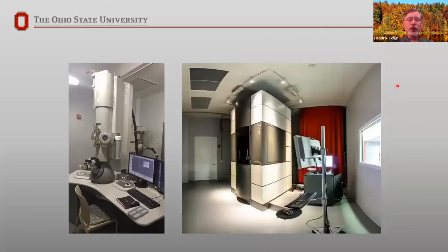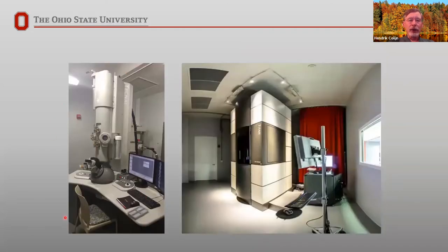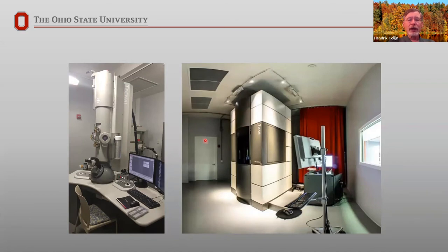The microscopes themselves look something like this. This is our Tecnai 30, with a 300 kV electron source at the top — electrons accelerated to 300 kilovolts — coming down through the condenser lenses, the sample on the center line, magnifying lenses below, and the viewing screen in the fishbowl at the bottom. Some of our other microscopes, like one of our Titans, have a similar column but sitting inside a box to minimize environmental disturbances, with people moved outside the room — a much bigger footprint, but necessary for ultra-high resolution.